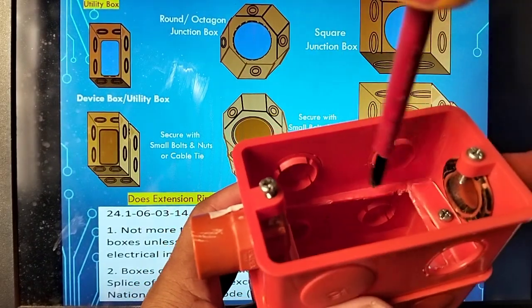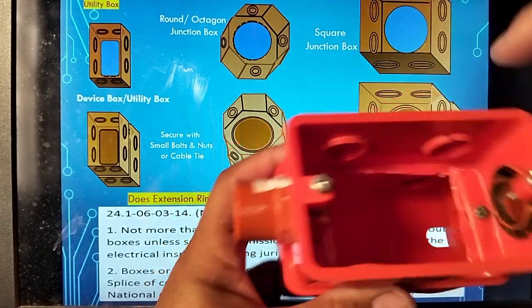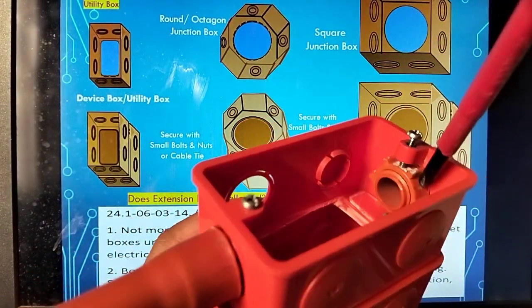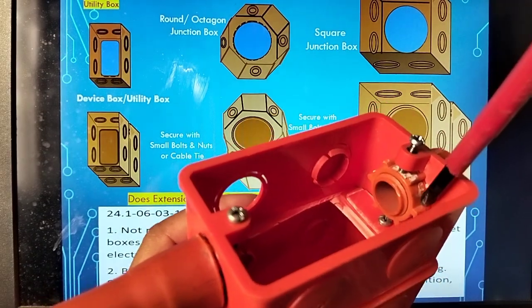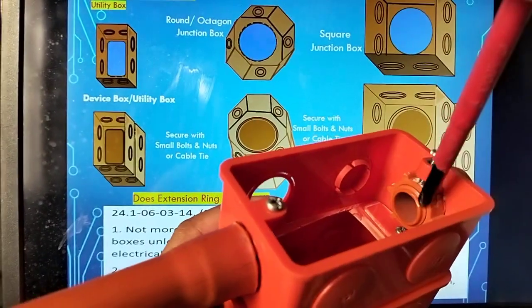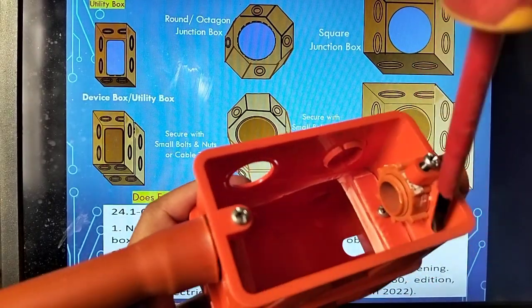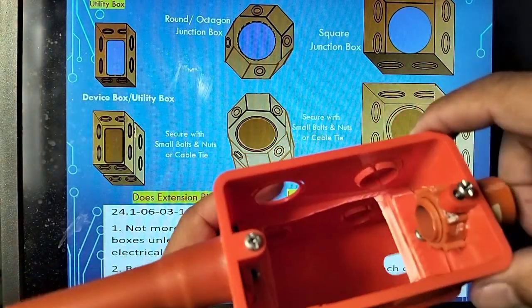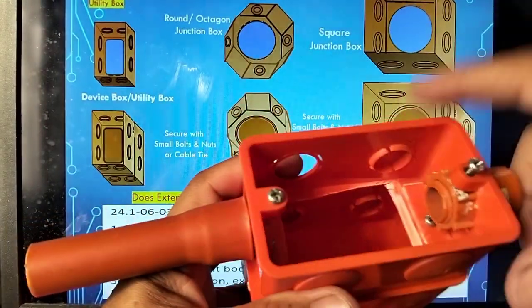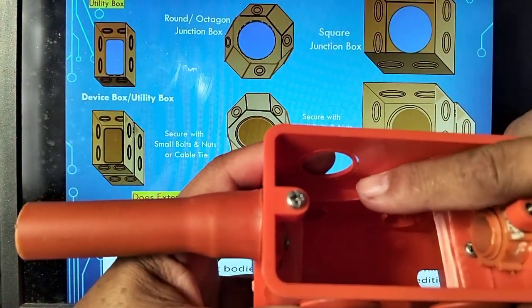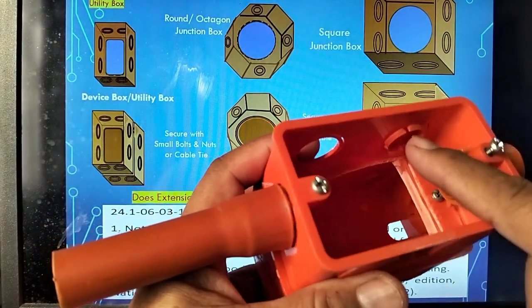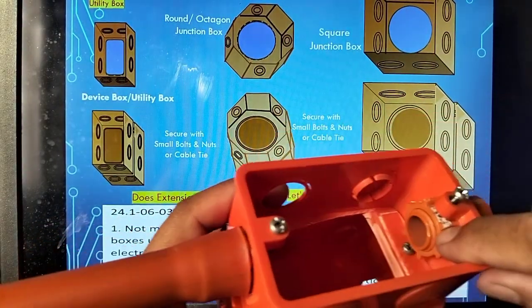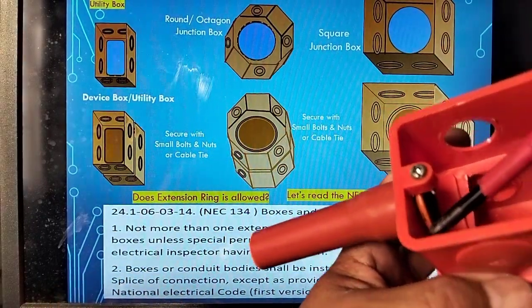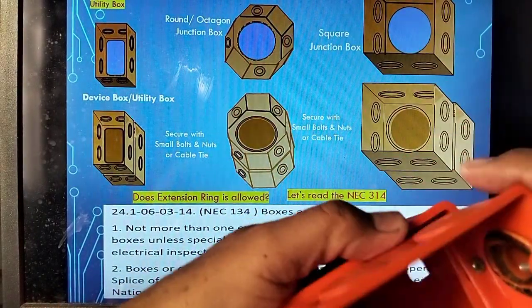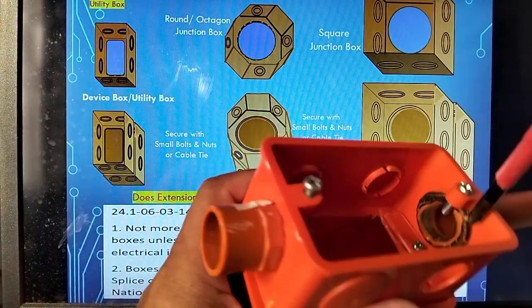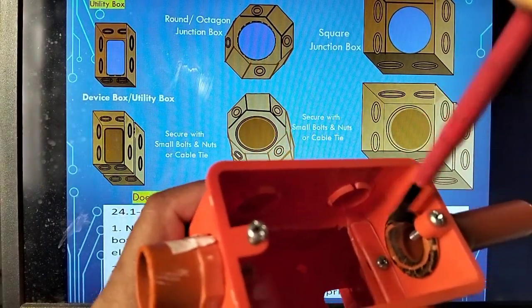you can have maximum box fill, whereas if you use the conduit connector, it will reduce the box fill, because this one may cause obstruction of the wiring. Let's say you have 8 individual conductors, and then you install the switch. It will cause obstruction, unlike this blind connector.